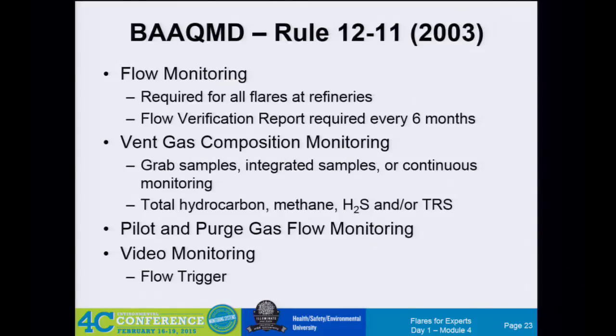Here's one of the interesting things: a flow verification report every 6 months on their Panametrics flow meters. Almost all the sites in the Bay Area have Panametrics. Every 6 months, everyone's still scratching their head, even after a decade, trying to figure out what exactly they're verifying. It's an ultrasonic meter. Those of you who've played with these know you pull out the transducers, confirm they're still there, and put them back in. There's nothing to calibrate, nothing to adjust, no gain knob to tinker with. So it either works or it doesn't. Yet people still do these checks every 6 months. It's a nice little side job if you want to retire and play with flow meters, I guess. There's a whole bunch of them out there to do.